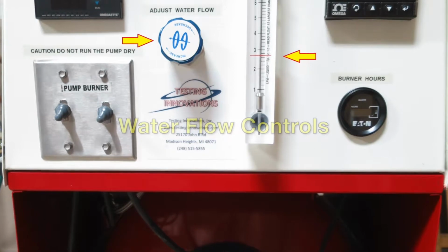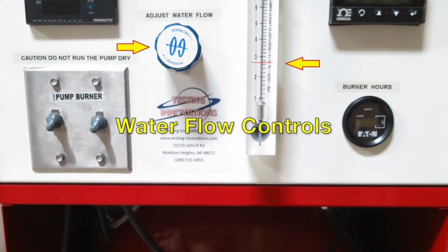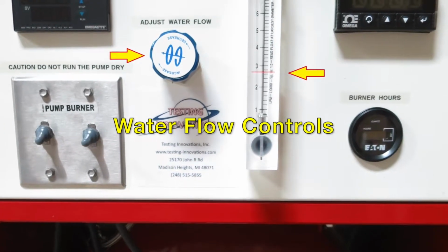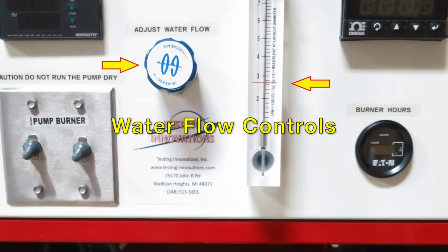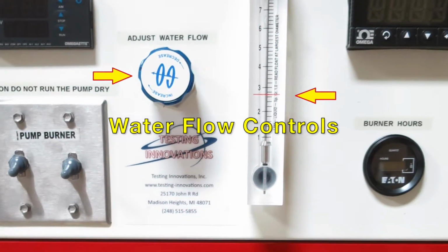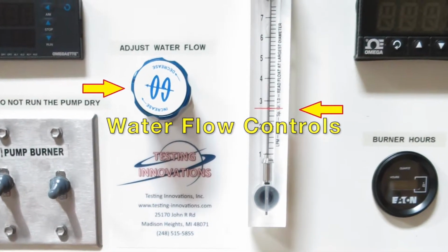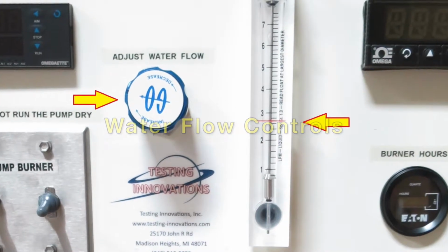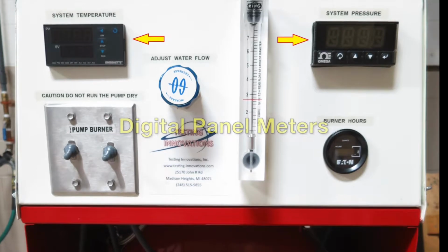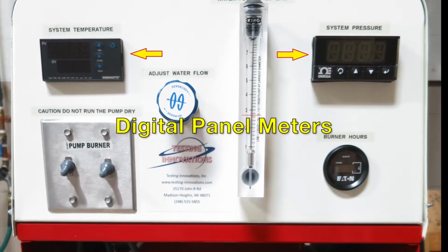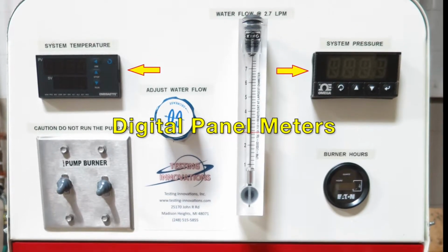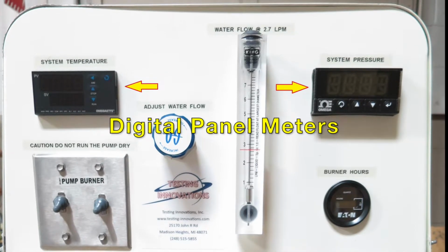The back pressure valve is referred to as the GO valve and controls the water diverted from the system into a recirculation loop. The water flow meter indicates system flow in real time and is measured by reading the largest diameter of the float. The digital panel meters are only output devices with the system temperature on the left and the system pressure on the right.